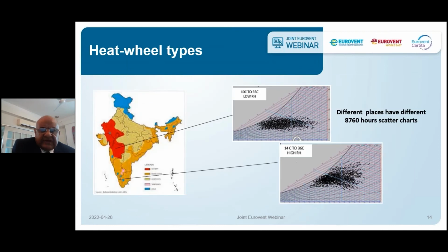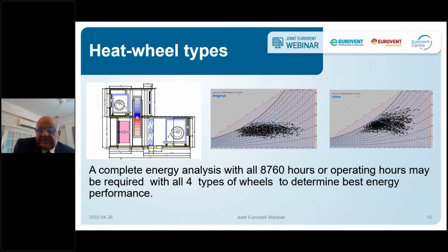Some studies have been done in India and other places with various combinations of entering dry bulb and wet bulb temperatures found in different parts of the country. Some places have low RH, which we call hot and dry. Some places have high RH, where the temperature does not go as high but the humidity is much higher. When we run an 8,760 hour analysis, we find that the energy spent differs with different pressure drops, and not all kinds of wheels result in the same energy consumption. This tells us it needs a very close look.